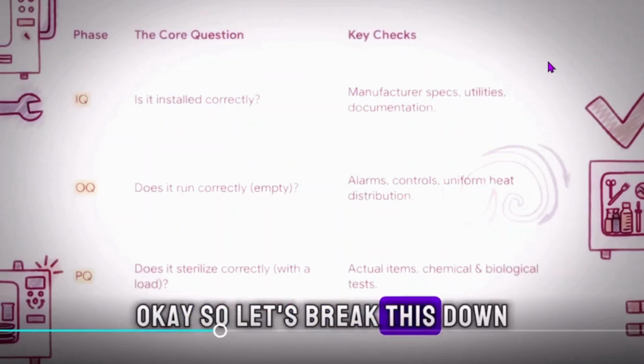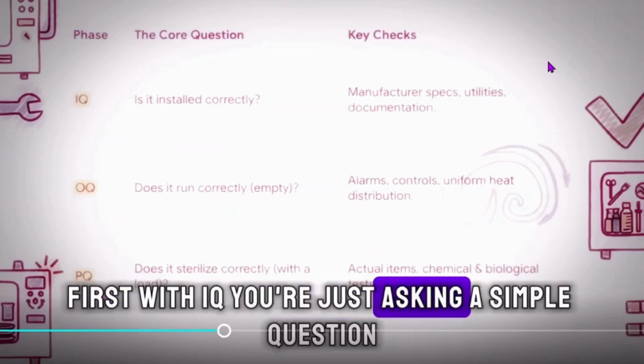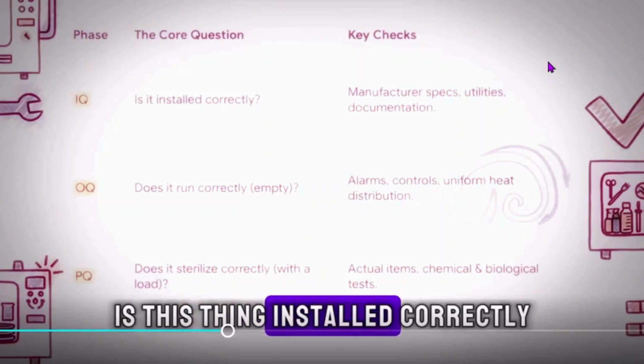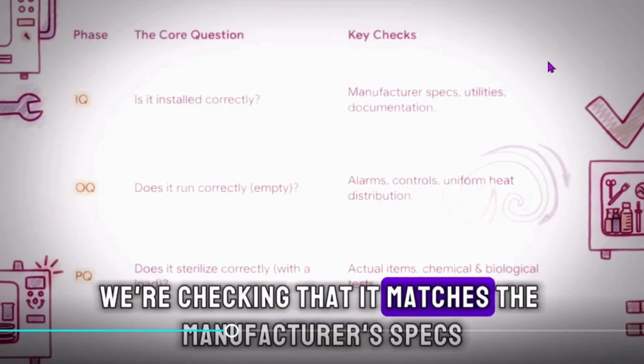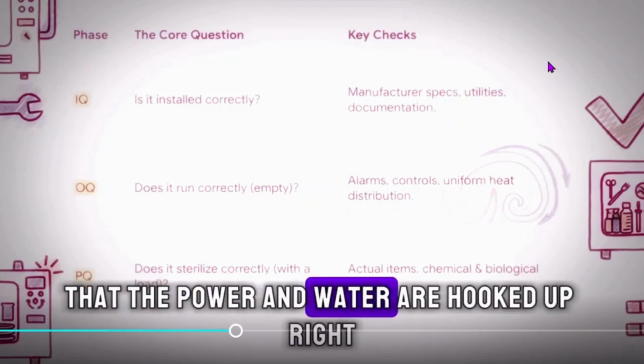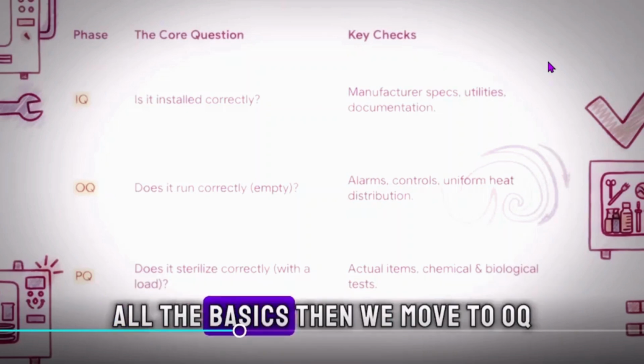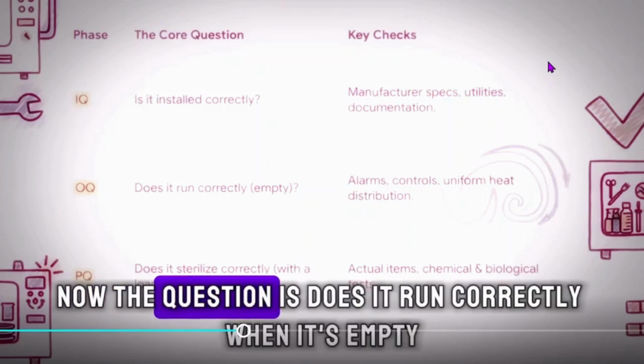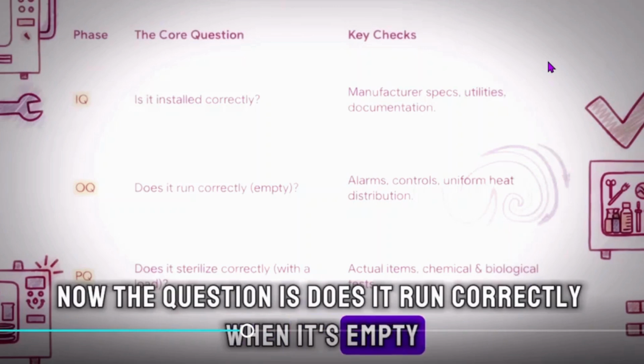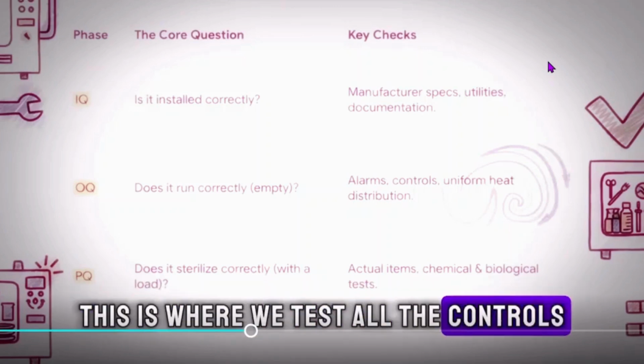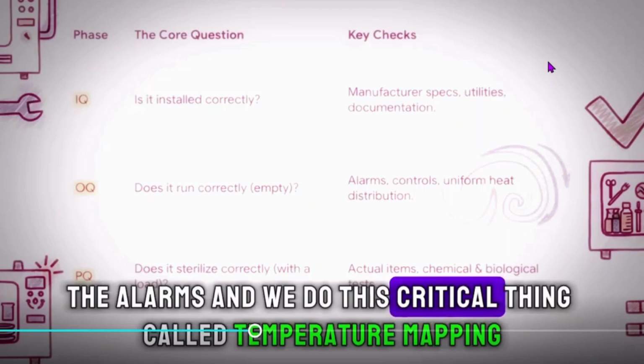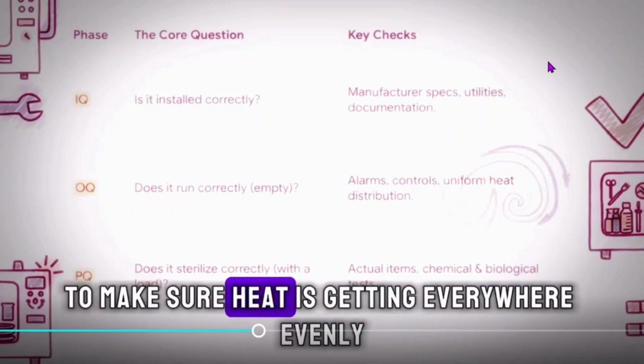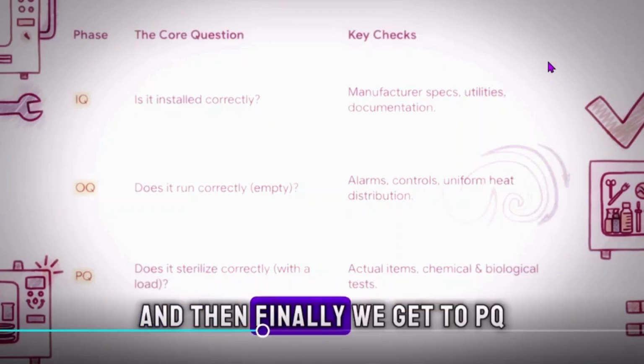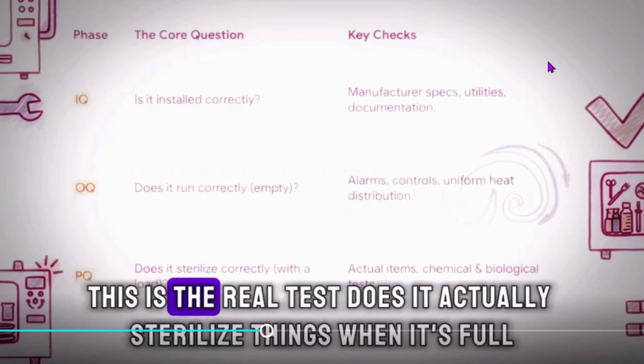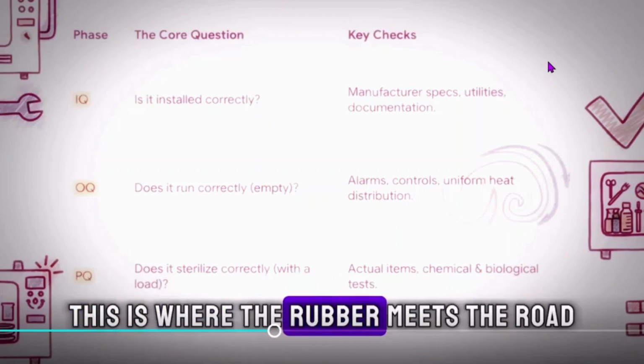Okay, so let's break this down. First, with IQ, you're just asking a simple question. Is this thing installed correctly? We're checking that it matches the manufacturer's specs, that the power and water are hooked up right, all the basics. Then we move to OQ. Now the question is, does it run correctly when it's empty? This is where we test all the controls, the alarms, and we do this critical thing called temperature mapping to make sure heat is getting everywhere evenly. And then finally, we get to PQ. This is the real test. Does it actually sterilize things when it's full? This is where the rubber meets the road.